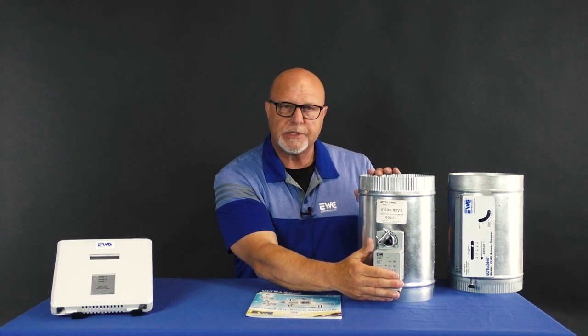You'd like to have a clean air filter. Let your system pressurize the ductwork for 3 to 5 minutes, at which point you will push the bypass setup button. This will send this smart bypass into its automatic setup mode, or learning mode, if you will. You will stand back and actually watch this damper operate and go through its setup process.